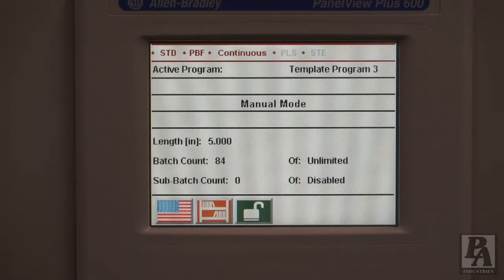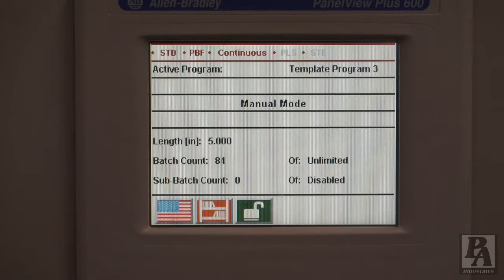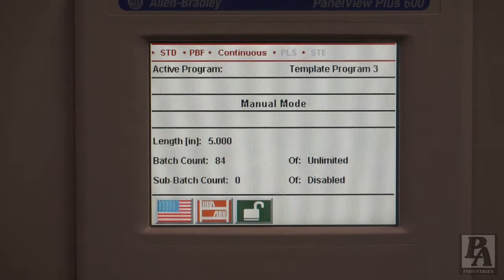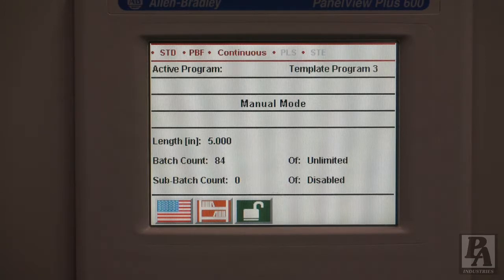Lastly, this line will also display if there is a servo drive fault. The last line will display a variety of messages, ranging from synchronization faults to external alarms. Each message adequately explains what has occurred, but for more information, reference your operation manual or call service at PA Industries. For a detailed explanation of sync faults and how to troubleshoot them, check out our videos — the links will be in the description.